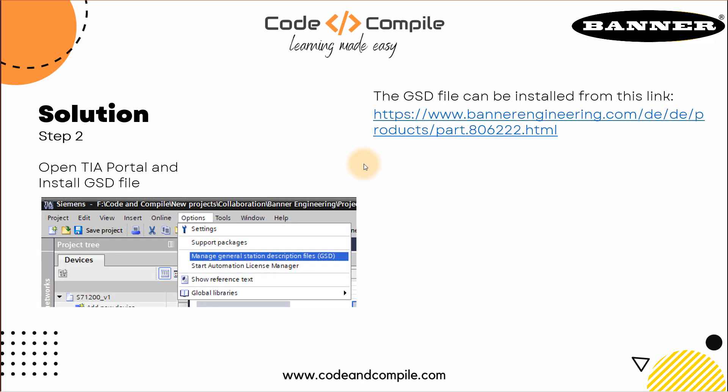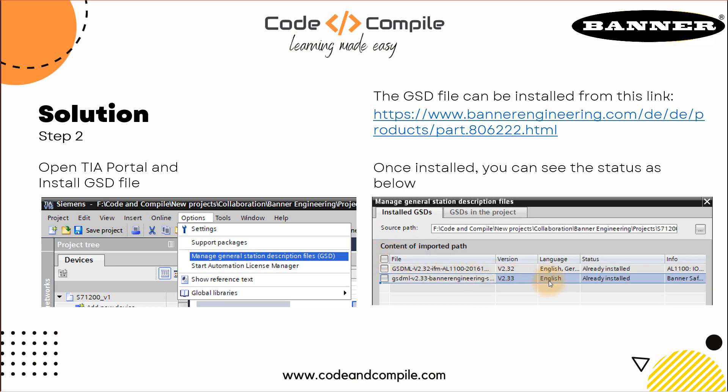Step two is we have to install GSD file in our TIA Portal PLC program. I'm using TIA Portal in this case. To install the GSD file, you can go to this link, download the file, and then you have to go to options and click on manage general station description files. Once you click that, you can install the file. If it's already installed, you will see your status here.